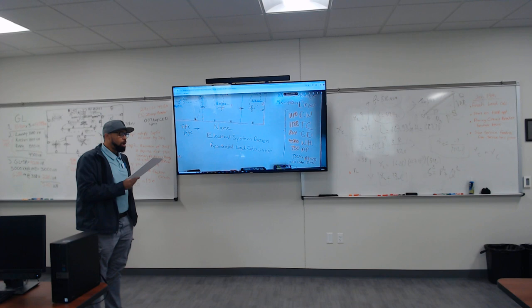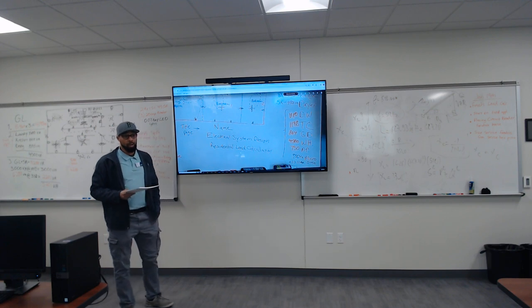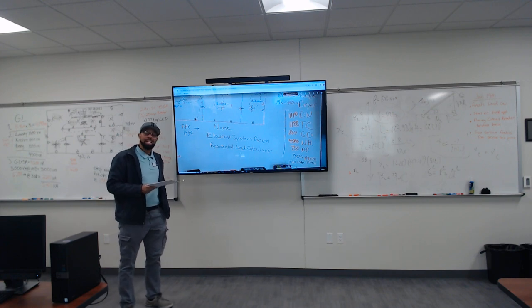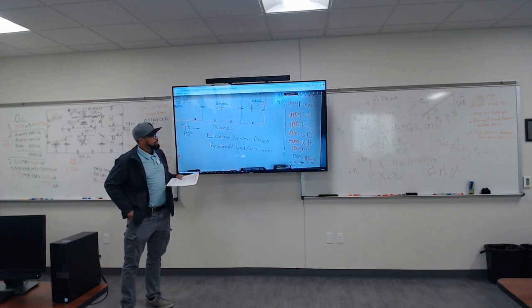Now, if it's four or more, we apply 75%. How do we do that? We add all of them up, and then we take that summation and multiply it by 75%. That's the total. So that's how we do that. So let's see what that is.